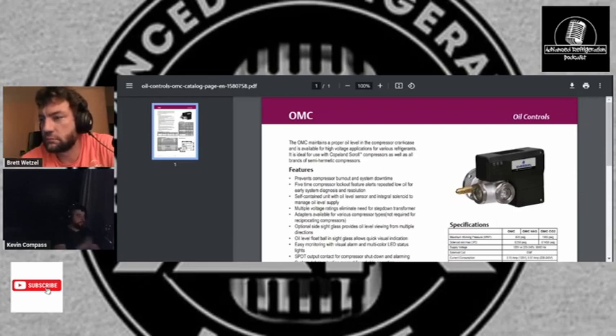Now, I will say this: in a pinch, I have taken an OMB and used it - the pressure rating's high enough for what you're going to be at. Your working pressure for whatever your receiver pressure is going to be is plenty high enough for an OMC in the middle of the night, because we've had a couple where an OMB failed or an OMC failed, and we've had to throw an OMB on it because a lot of supply houses don't stock OMCs yet.